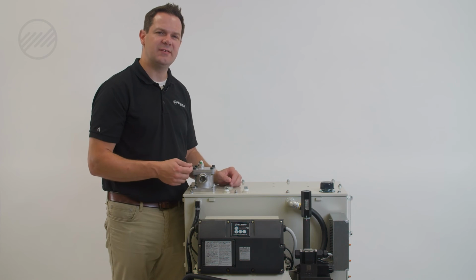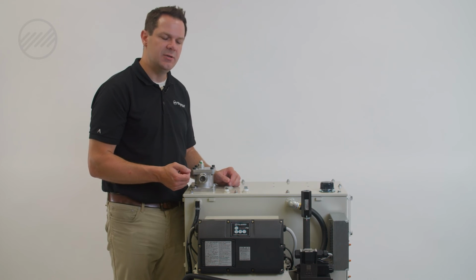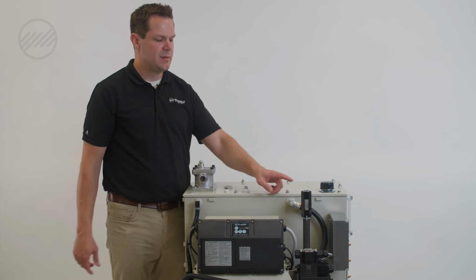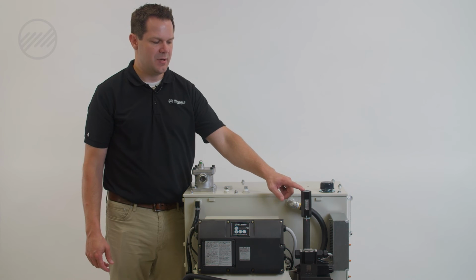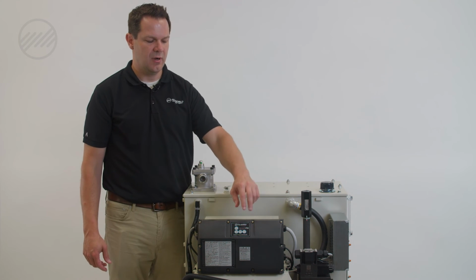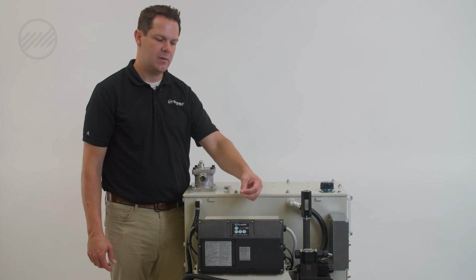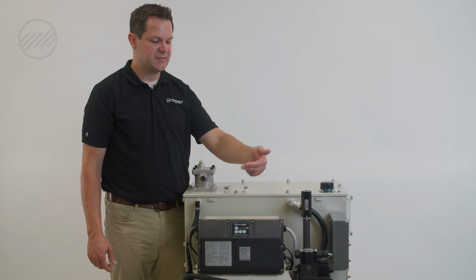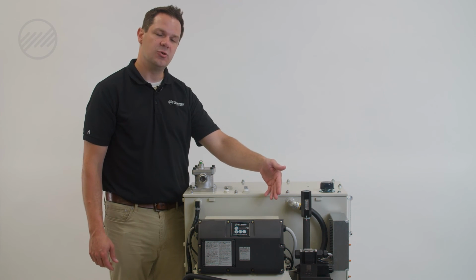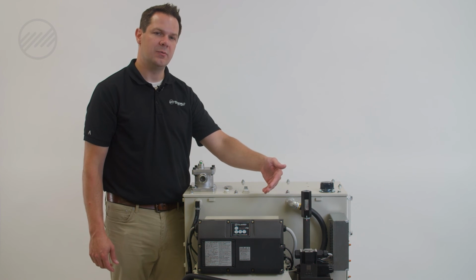Ambient temperature can also be a factor. If you've exceeded 104 degrees Fahrenheit in your shop, it's possible, given the cycle times and duties and pressure settings, that it may not be able to overcome that heat. If all of these have been verified, you can check your motor RPM again by deadheading or capping the pump to see if our RPM will decrease. If not, and it still stays high, you may have leakage through the pump and may require replacement of the pump.